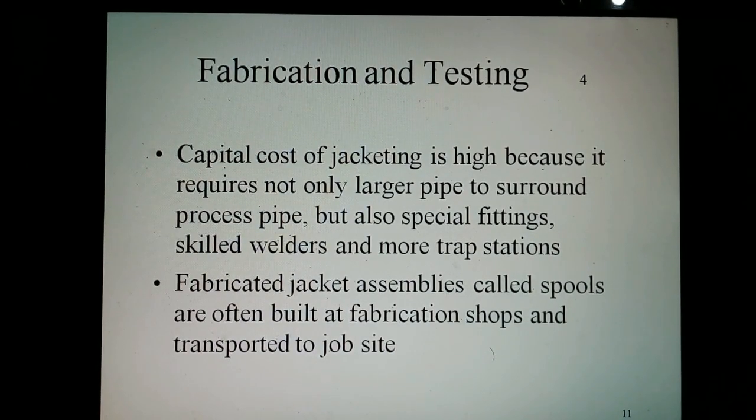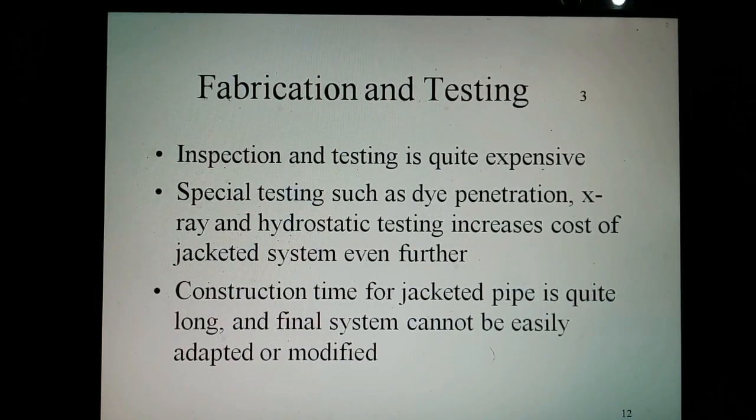Fabrication and testing: The capital cost of jacketing is high because it requires not only a larger pipe to surround the process pipe, but also special fittings, skilled welders, and more trap stations. Today, fabricated jacket assemblies called spools are often built at fabrication shops and transported to the job site. Inspection and testing is quite expensive. Special testing such as dye penetration, X-ray, and hydrostatic testing increases the cost of a jacketed system even further. Construction time for jacketed pipe is quite long, and the final system cannot be easily adapted or modified.